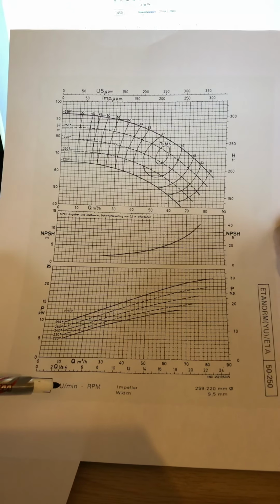So the only two values that you'll be given are the flow rate of the water, which is this Q. You'll find it on this axis and then you just move up. So in this example, it's 30. And then the impeller diameter, which is 220. And as you can see, if you move up from that 30, and that 220, they cross each other right at that point. Okay, so that 220 and the 30 cross each other right there.